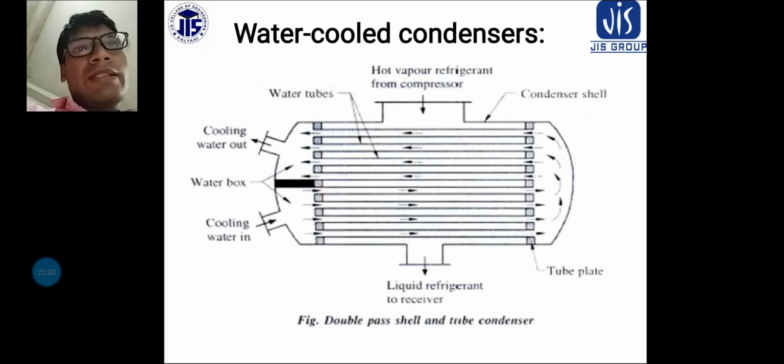Though the counterflow principle with the double tube condenser makes good use of the water available, the large number of joints and connections needed in large installations increases chances of leakage. These condensers are difficult to clean and do not provide enough space for separation of gas and liquid.